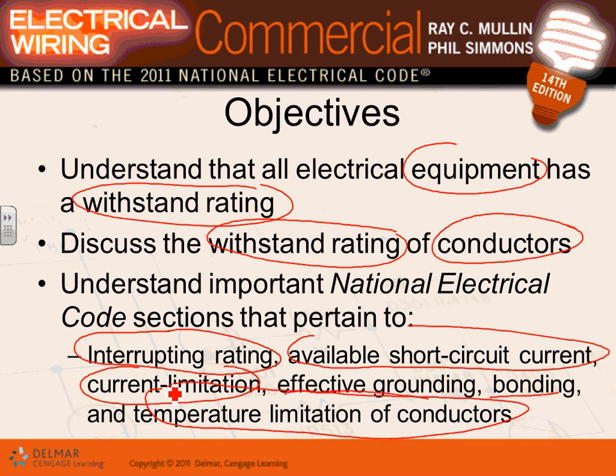What happens when you have a short circuit condition is the temperature starts rising inside the conductor, higher and higher. You're going to cook that conductor. Two things will happen. First, if it's insulated, the insulation starts melting. Second, if that's not enough and it continues, the copper or aluminum conductor starts melting. Can you imagine melting copper inside these conduits? Can you guys imagine why we have conduits to start with? If you're lucky, you only burn your electrical equipment. If you're not lucky, you've just burned your building. So it's a big deal.